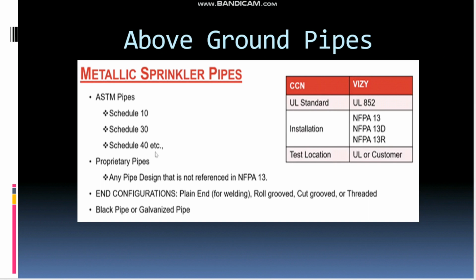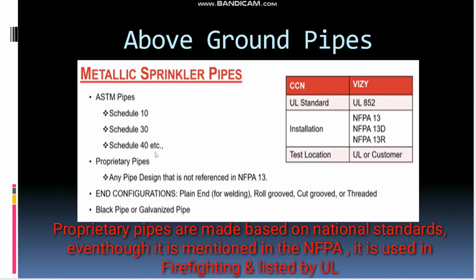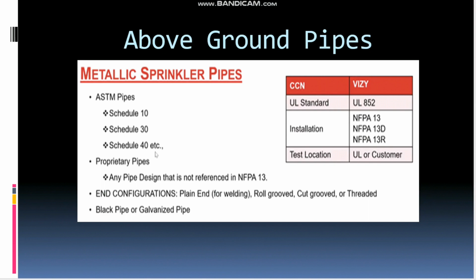So here is the list of different ASTM pipes: schedule 10, schedule 30, schedule 40. Mostly for firefighting we use schedule 40, the thicker pipes. And there is a special term you may not be aware of: proprietary pipe. Proprietary pipe means any pipe design that is not referenced in NFPA, because some parts of the world use different types of pipes, and if it is not mentioned in NFPA, it is called a proprietary pipe. Even those pipes are acceptable as per UL listing, meaning they are eligible for UL listing. They will perform some different type of testing, so that pipe is called a proprietary pipe.